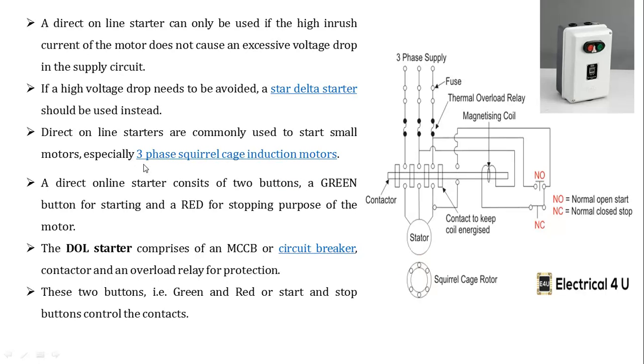Which type of small motors? Actually, there are two different types of three-phase induction motor. One is the squirrel cage induction type, and the second one is nothing but the slip ring type. But here we have to start the small motors, especially a three-phase squirrel cage induction motor. A direct online starter consists of two buttons, which are shown in this actual picture. That is nothing but the green and red. These are the two buttons for starting and stopping. So the green button is for starting and the red button for stopping the motor.